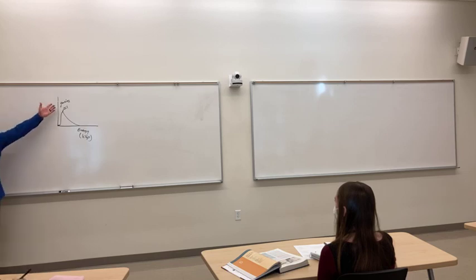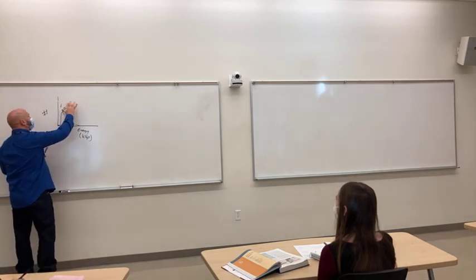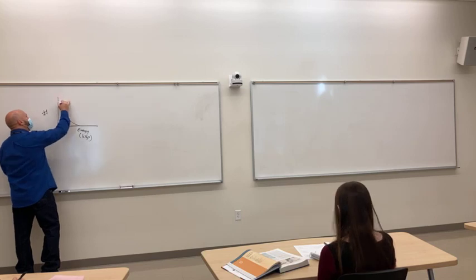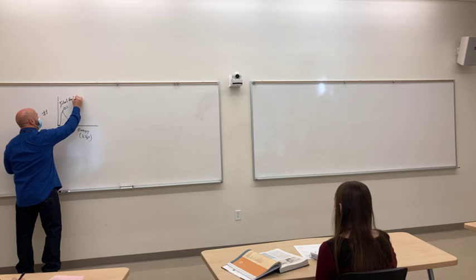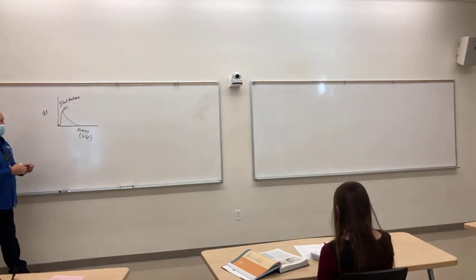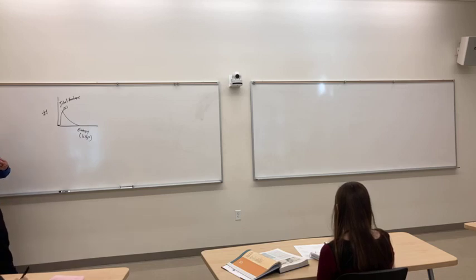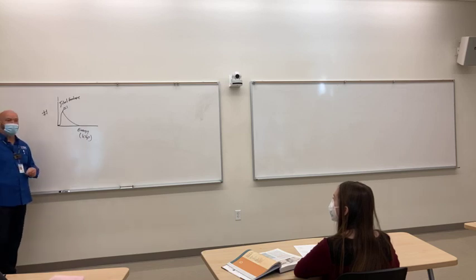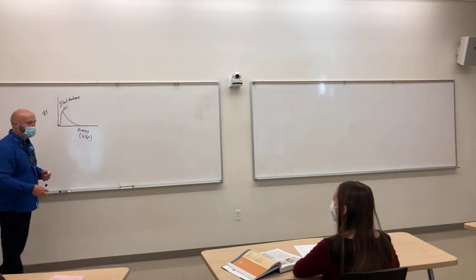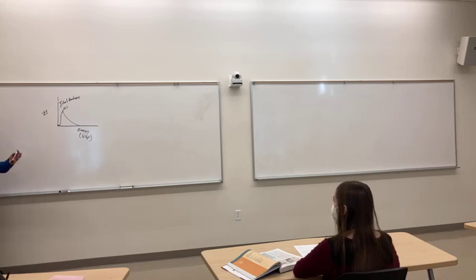Or I'm sorry, that was the X-ray tube. I kind of gave that away. Yes. The tube, the oil, we'll say envelope. Okay, so now it's the housing. So the housing holds the oil in, and if you remember, we've got two different reasons for the housing. One is to protect the tube from you, and one is to protect you from the tube, right? So it limits the amount of leakage radiation, or radiation outside of the collimated area, but it's going to be made of metal as well.